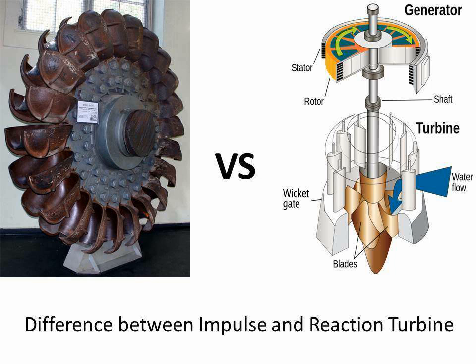Impulse turbines. In an impulse turbine the potential energy, or the head of water, is first converted into kinetic energy by discharging water through a carefully shaped nozzle. The jet, discharged into air, is directed onto curved buckets fixed on the periphery of the runner to extract the water energy and convert it to useful work.